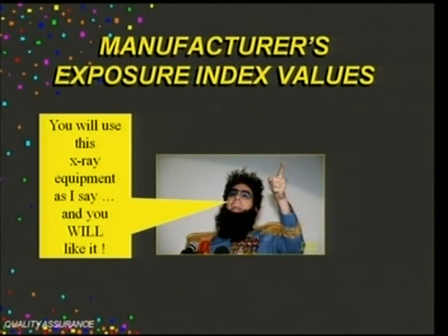So you want to make your techniques not at the saturation end and not out of range, obviously. Those are the two danger zones, we'll call them. So don't just listen to your manufacturers; use the equipment as you want to use it. I always tell the students, don't let your equipment tell you what to do. You tell the equipment what to do, okay?